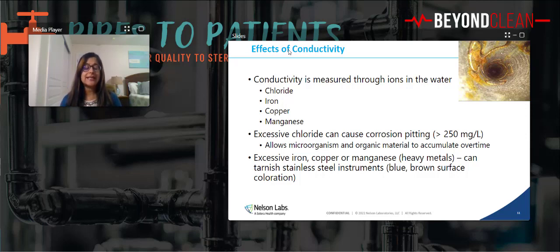And this was only reprocessed six times. So you can understand that reprocessing six times and already seeing this damage means this device is not good for users, so of course we failed it. But it's something you want to consider - looking in the lumens - to ensure that the outside may look beautiful, but you want to look inside and make sure the inside also looks as pretty as the outside.